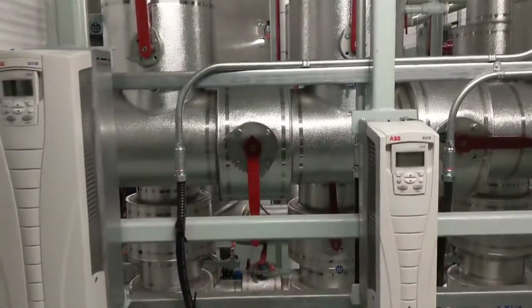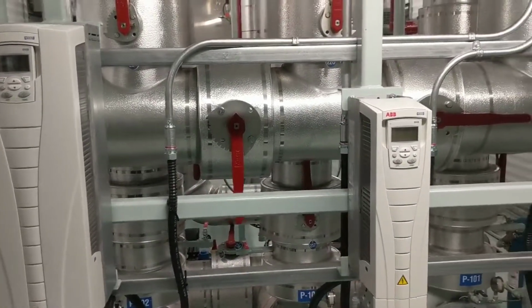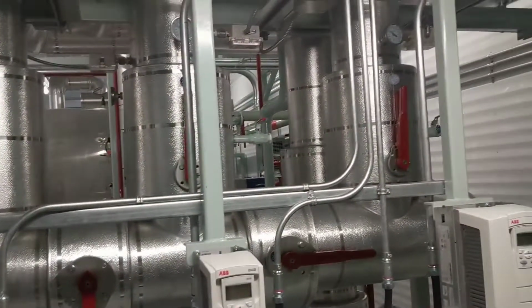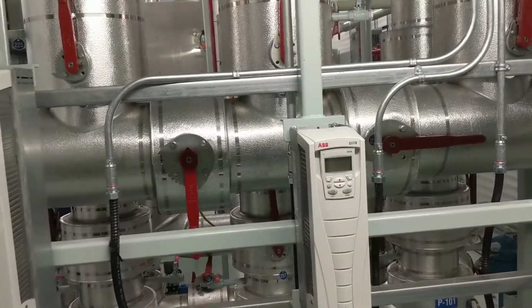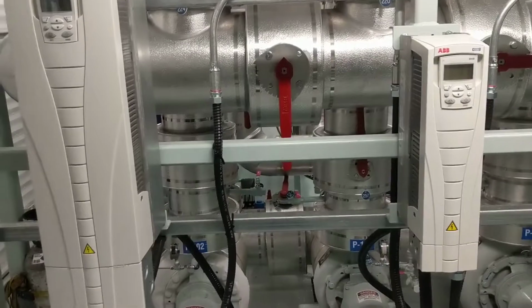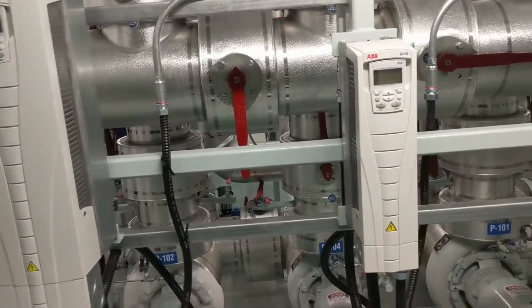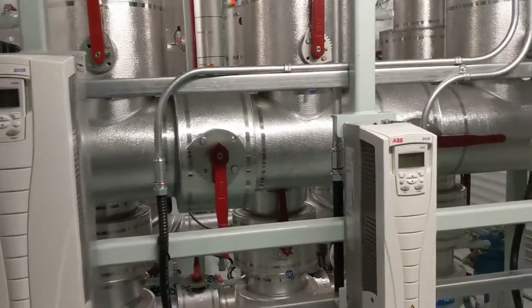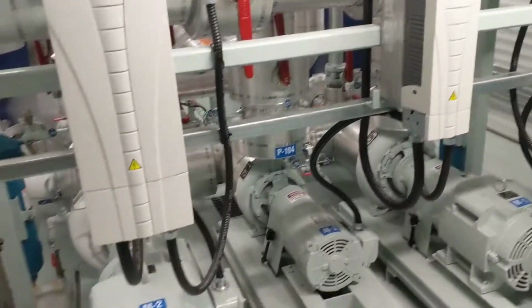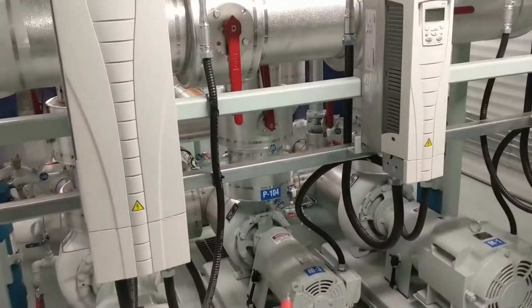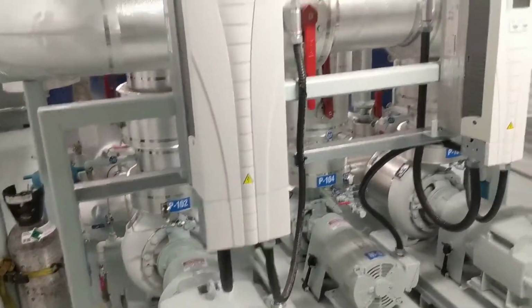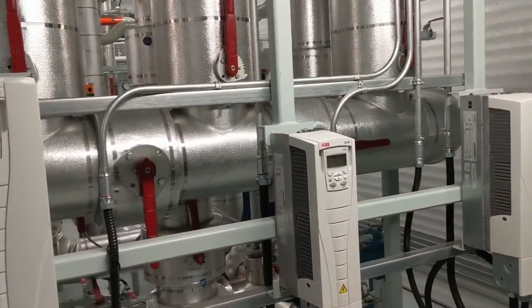So the brine tanks, there's heat floor and then the 2 cold floors, and those 2 cold floors are the balance tanks, and the curling rink can kind of go with either one. When it needs to be changed, it needs to be changed both via the valves and in the computer system. So that's something that you should always make sure you have someone who really knows what they're doing change that. It's important that it's done correctly in order to keep things working properly. So the curling floor can never run by itself. It always has to run with one of the other 2 floors, and currently it's set up with the TC arena.